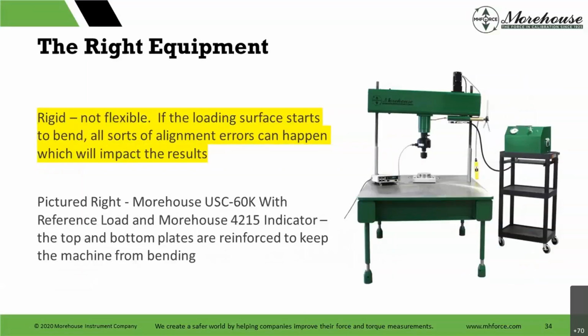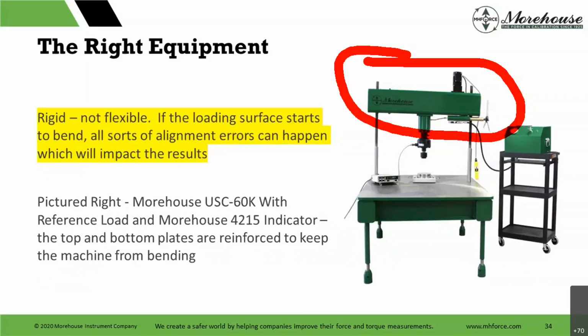Rigid, this is one of our scale calibrators. If there's deflection all over in this beam or here, what's going to happen to my device on my scale? I'm going to have something that's slightly off center. So when we say rigid, we mean not flexible. If the loading surface starts to bend, all sorts of alignment errors can happen, which will impact the results. This usually comes up when you do your reproducibility, your R&R between techs. It will come up in that because you may get drastic numbers if you have a lot of bending in your system.